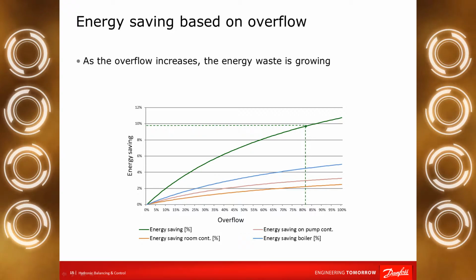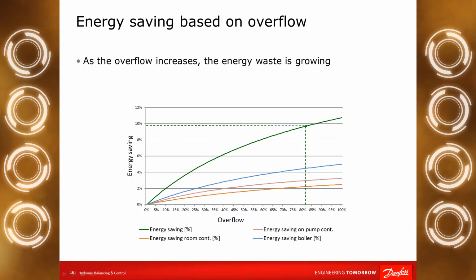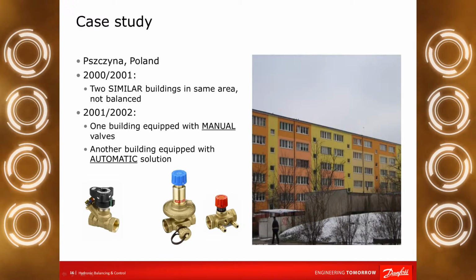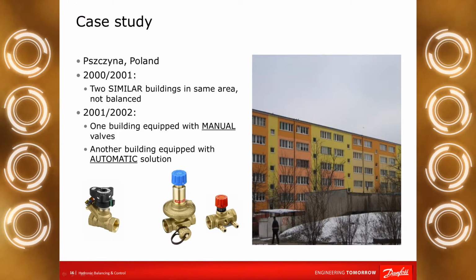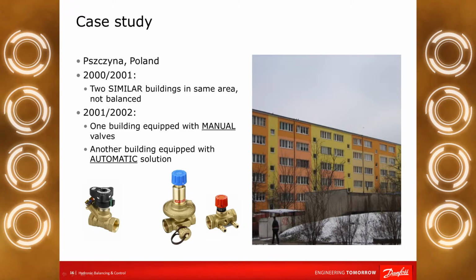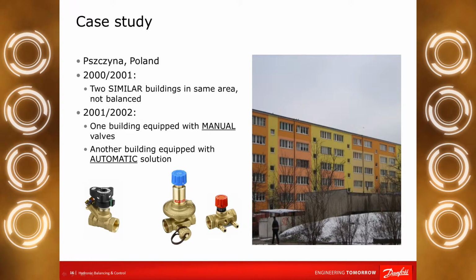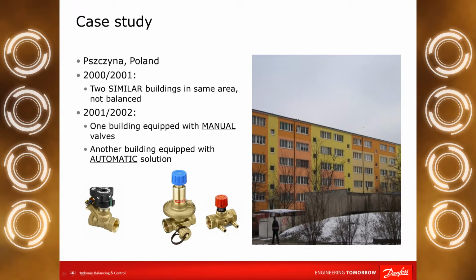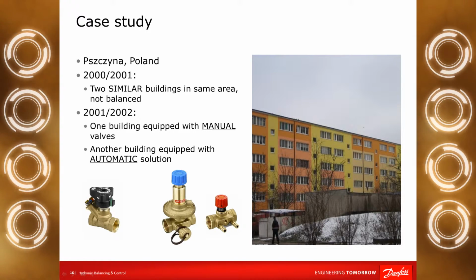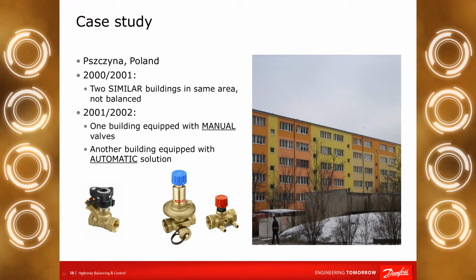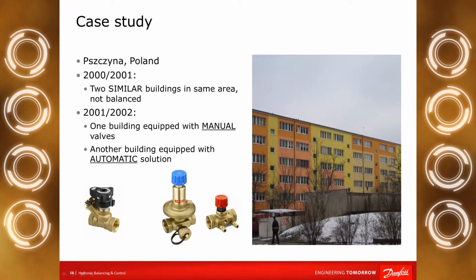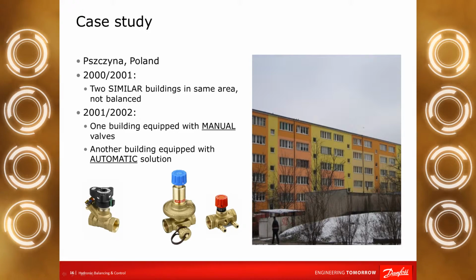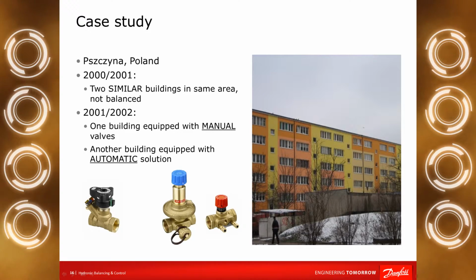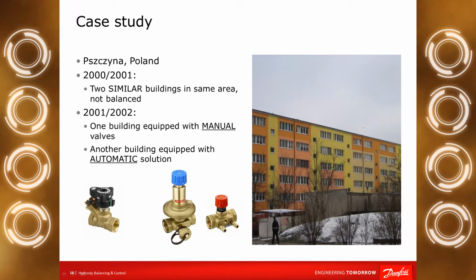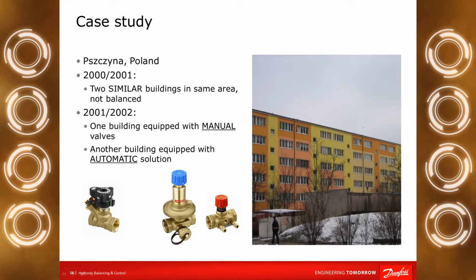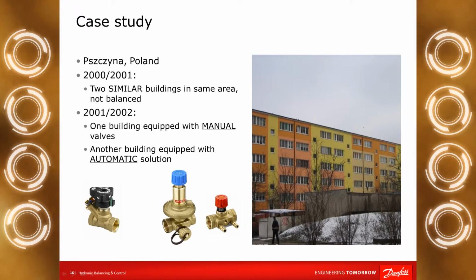Let's check how the energy saving calculation fits on a theoretical level compared to reality. To that, I would like to show you a case study from Poland. We had 2 buildings which were not properly balanced, but the heat measurement was done in year 2000 and 2001. In the summer of 2001, we renovated the 2 buildings. One of them was equipped with manual balancing valve and properly balanced, commissioned. And the other building was equipped with automatic balancing valve, delta P controller, and also commissioned.